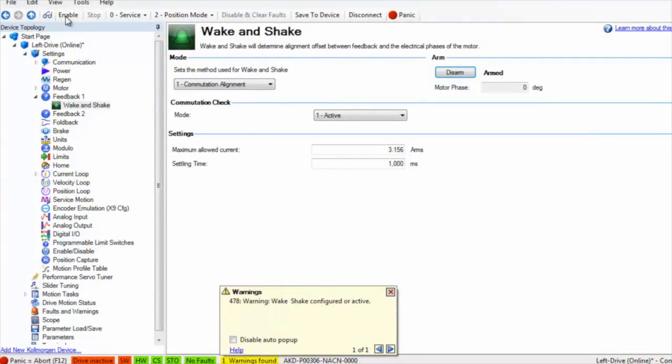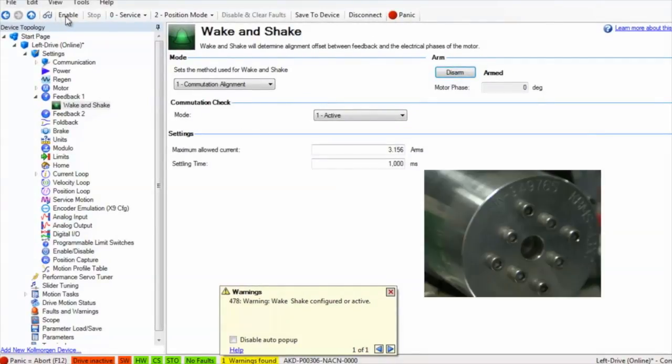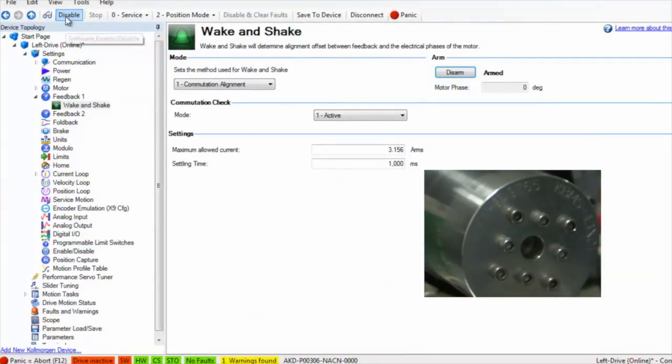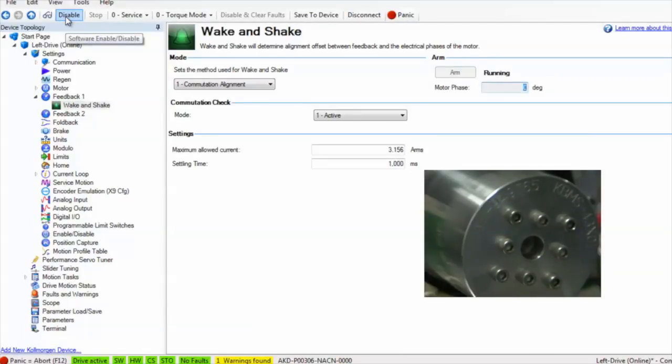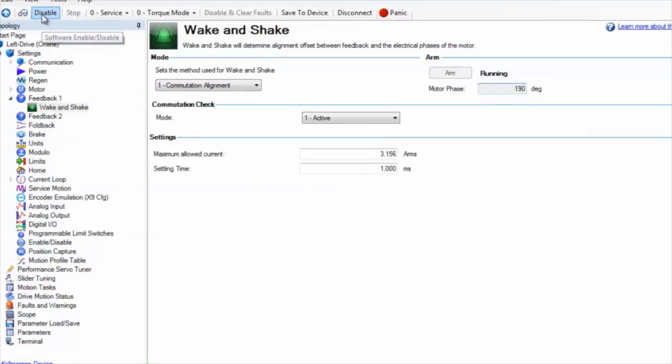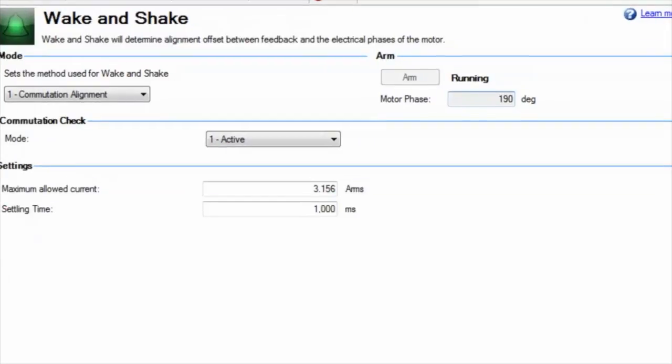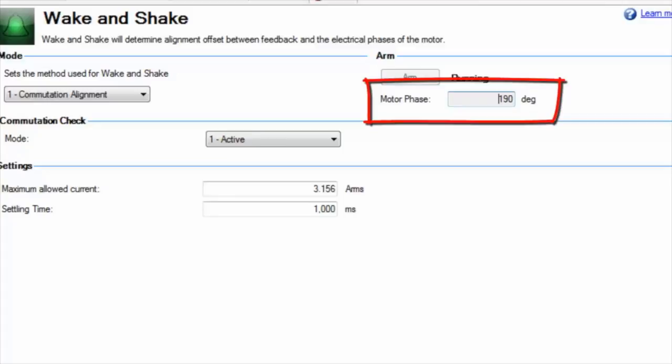Then click arm. When enabled, the drive will poll the motor, meaning that it will place a DC voltage across windings U and V. The motor will snap into position. Since the sine encoder is an absolute device, the drive will calculate the motor position after polling and will set the motor phase.